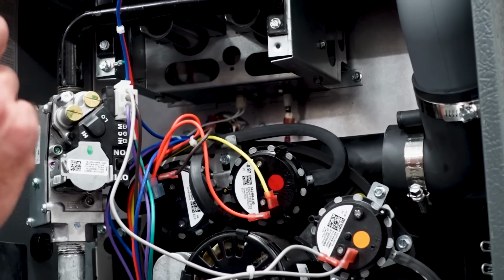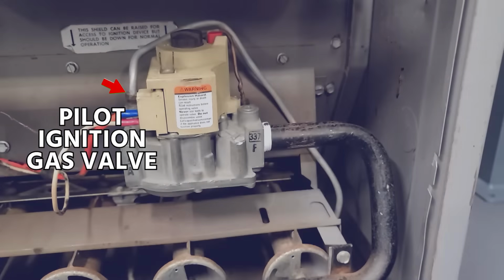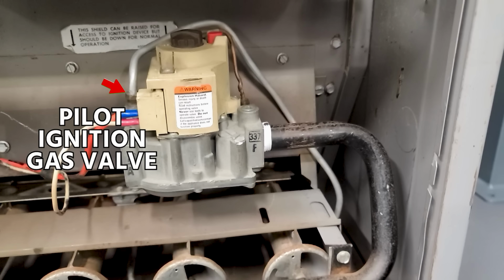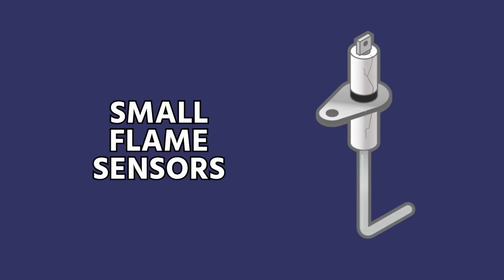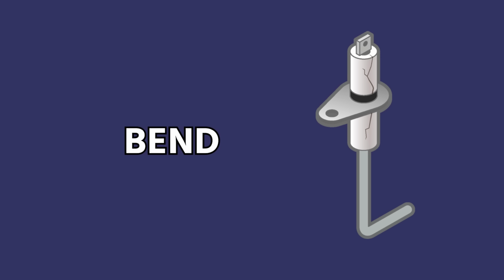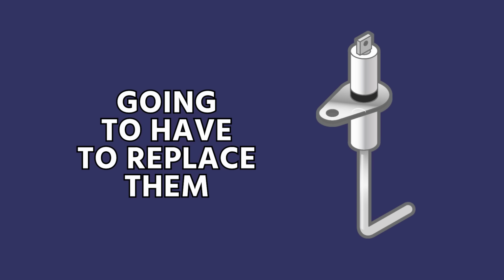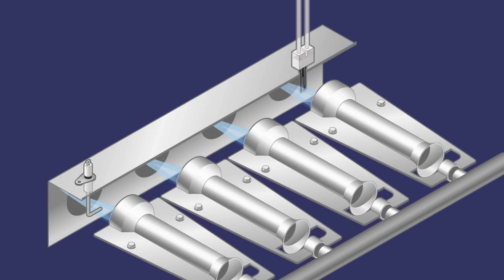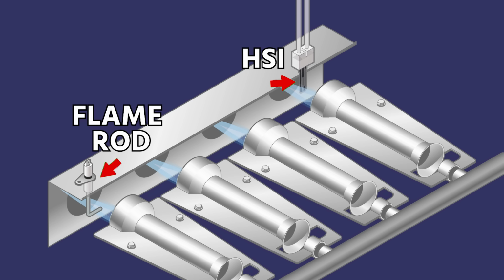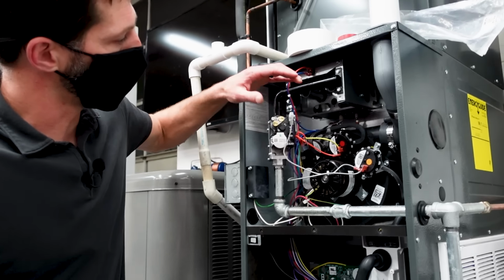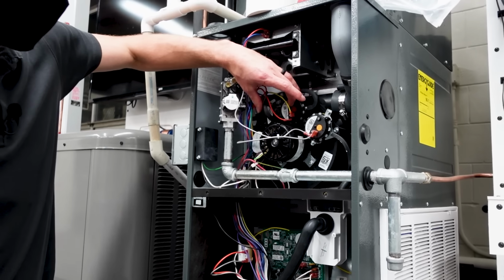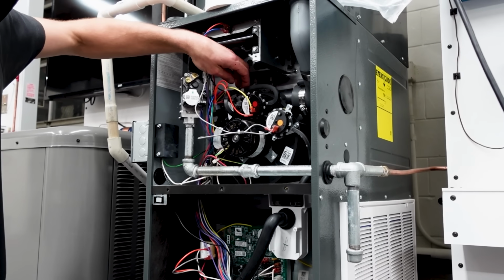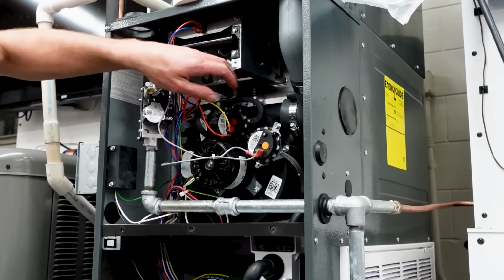Now, there are the small flame sensors on the pilot ignition gas valves, and they're real small, and those deteriorate over time or bend and just get out of whack. Yeah, you're going to need to replace those, especially on smart valve systems, where you have the HSI and the flame rod all as one pack, and you just replace that whole assembly. You can notice which pressure switches are for the high and low, just because it's attached to this inducer motor.